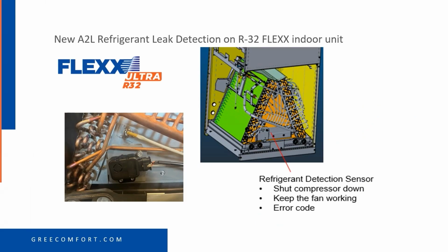And of course, with all of your R32 equipment, it's going to come with a leak detection sensor, an A2L refrigerant leak detection sensor on that unit. As you install this, you'll notice the new sensor in there. Depending on horizontal or vertical installation, you'll want to move that sensor. All you have to do is loosen the screws and move it over to the lowest point. It needs to be at the lowest point.